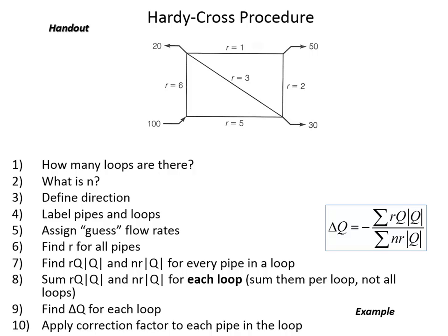So if you had to guess, which one of those do you think is going to have more flow? The pipe on the bottom, the horizontal pipe, or the vertical pipe? Of these two, some of the water is going to go through this one, some of it's going to go through that one. Which is going to have more flow? So the horizontal one is going to have more flow because there's less resistance. The R value is lower, which is conducive to more flow going through it.